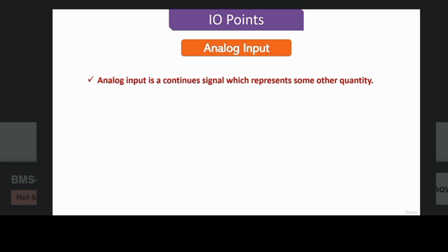Analog input is a continuous signal which represents some other quantity. Analog inputs are used to monitor the values from sensors like temperature sensors and pressure sensors, or they can be used to get the feedback from the field devices like valve actuators and damper actuators. Analog input can be a 0 to 10 volt DC signal, or it can be a 4 to 20 milliampere current signal, or it can also be a resistive signal from a thermistor.